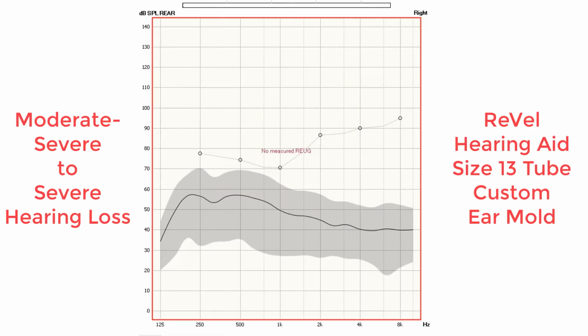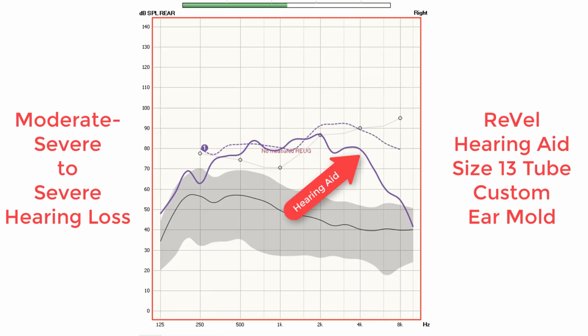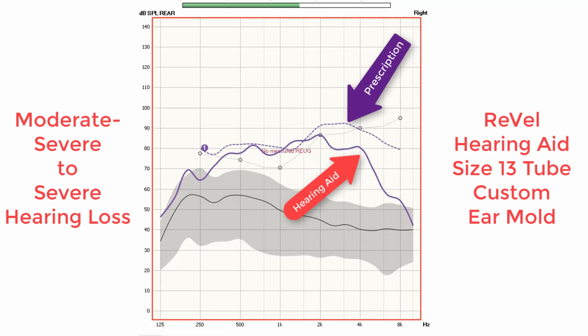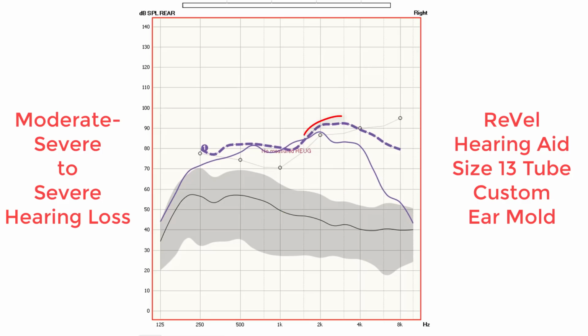As I start the test here, what we're trying to accomplish is get that solid purple line, which is the amplification coming out of the hearing aid, to overlap with the hash mark line, which is the prescription for this type of hearing loss. And as you can see, we're getting pretty close to that prescriptive target, but this is after making some additional changes in the hearing aid. I wasn't quite able to get it all the way up to a severe hearing loss prescription in those high frequencies. And this is, of course, me testing the hearing aid inside my ear. So it may be a little different for another person's ear.